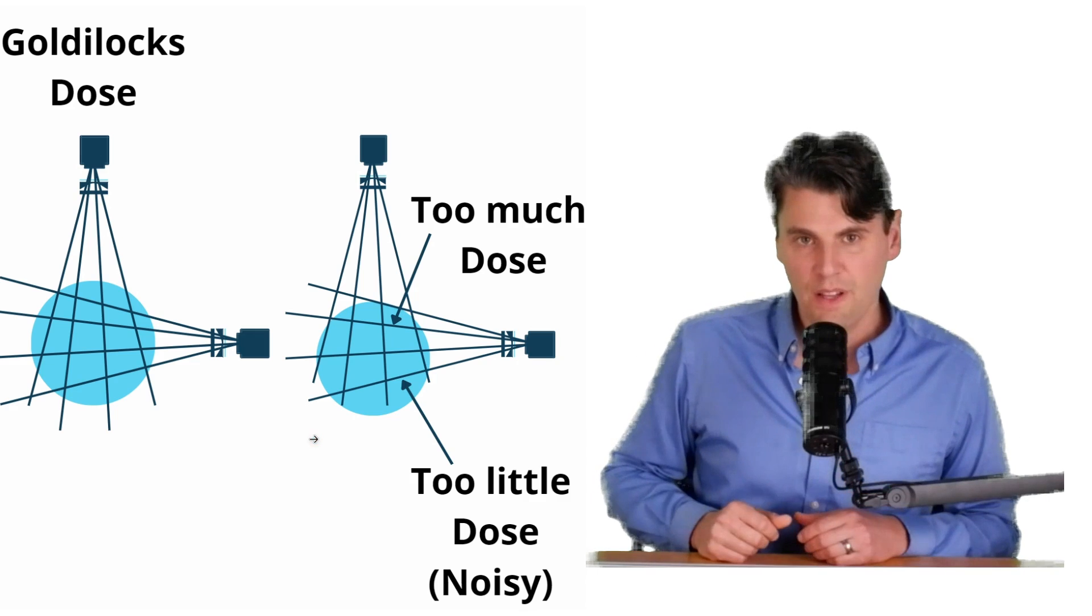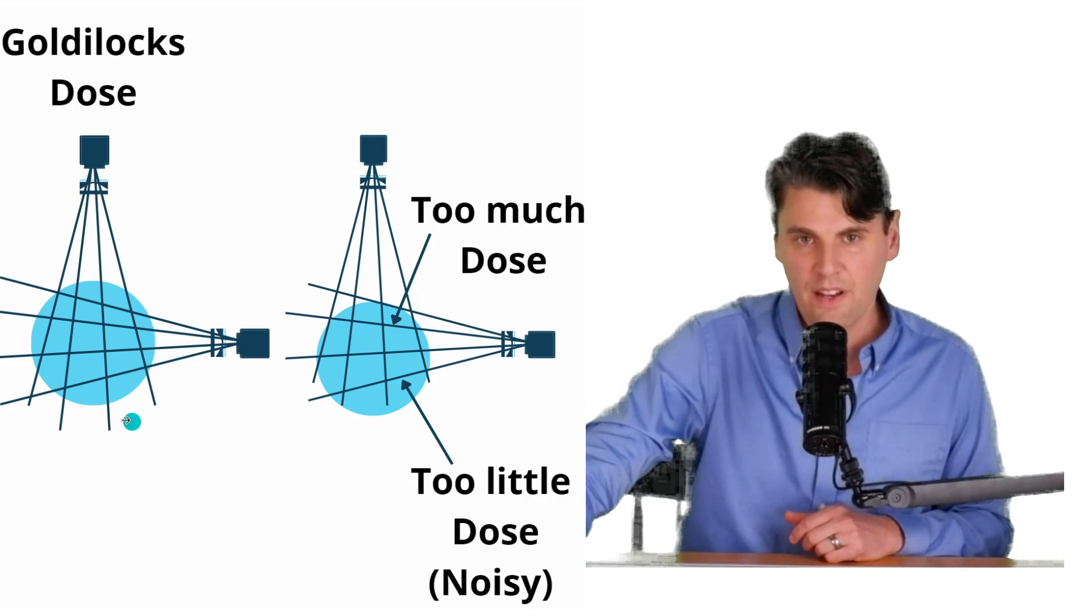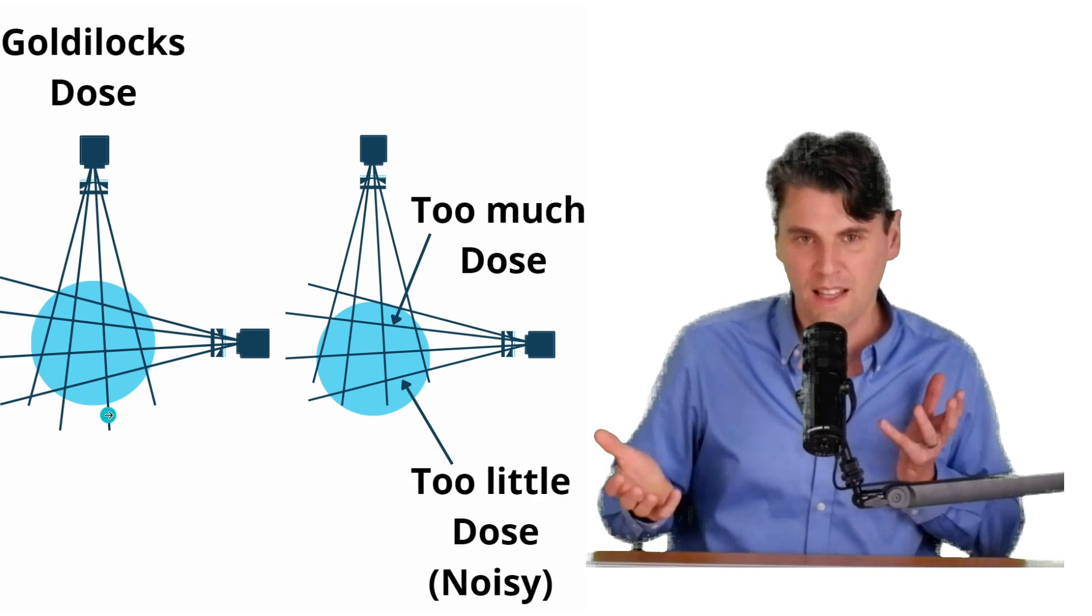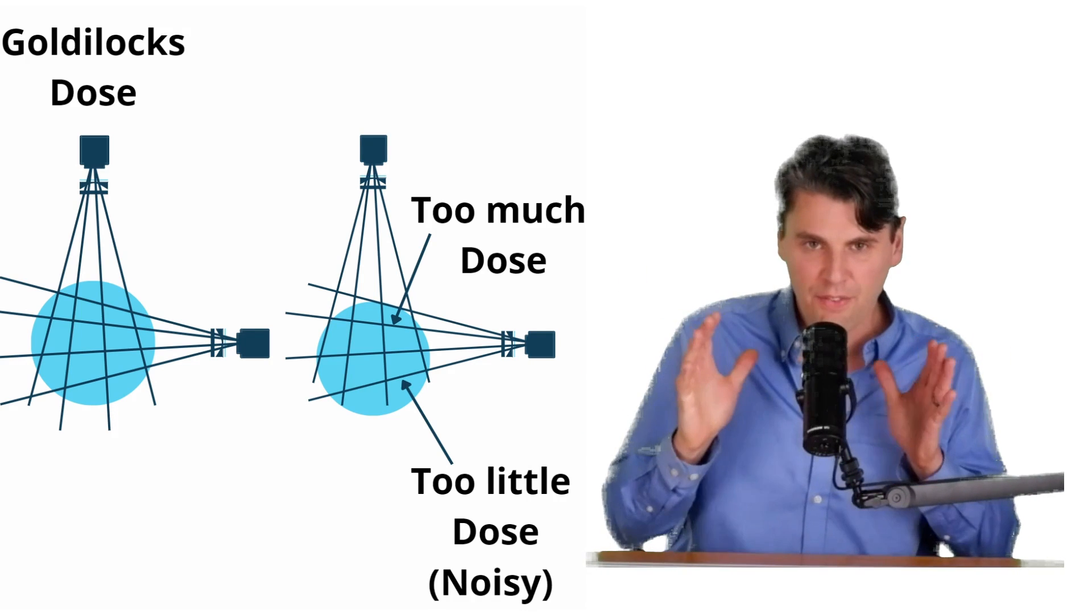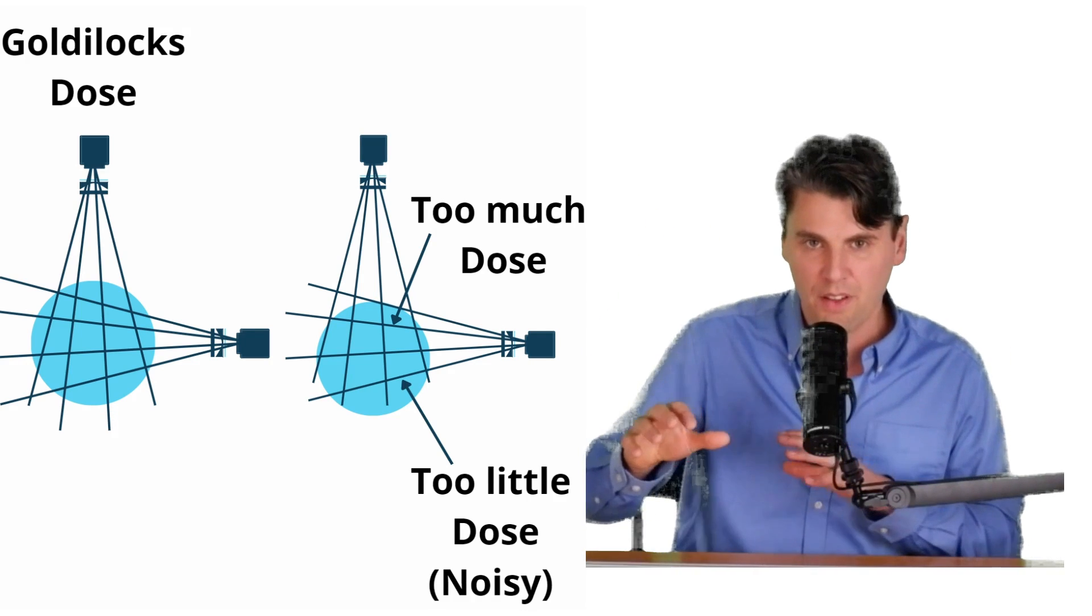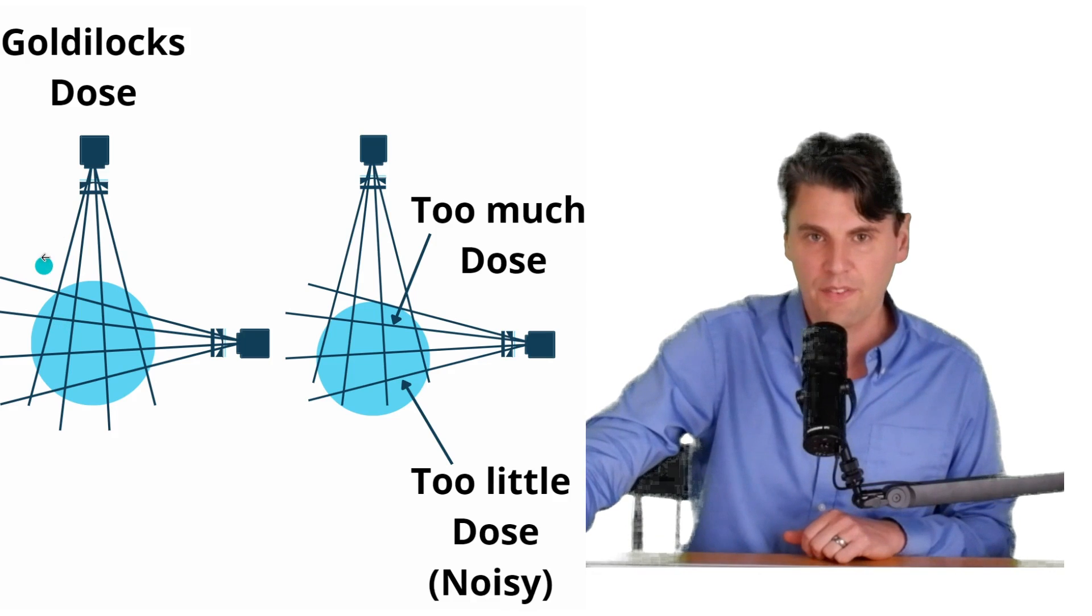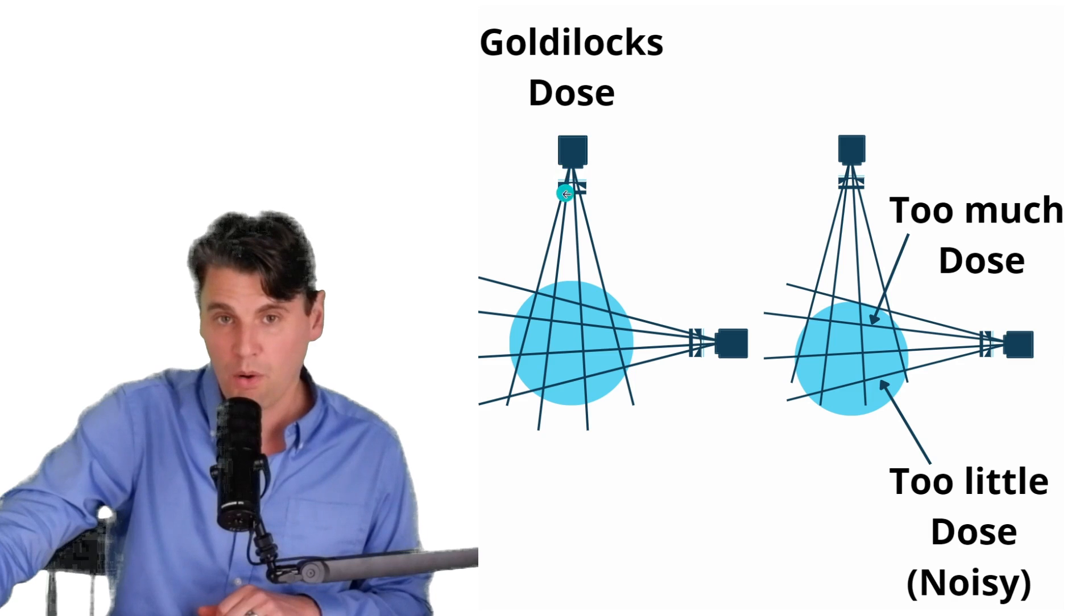If we look at two different views, again, in the left scenario here, this is what we call the Goldilocks scenario where it's just right. We've got the left-right position's good, the up-down position's good. And if you look at some of the different rays, you can see that we have a relatively good balance because we're going through the bowtie and then the object's relatively well-centered.